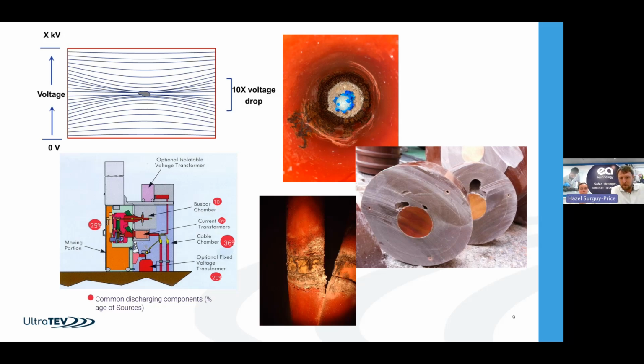And the final picture is an old favourite. Phasing tape has been left on the cable termination, and that over time has started to cause an area of high stress and eat away at the cables, leading to failure, or potential failure in this case. I mentioned that high stress is the root cause of PD, really.